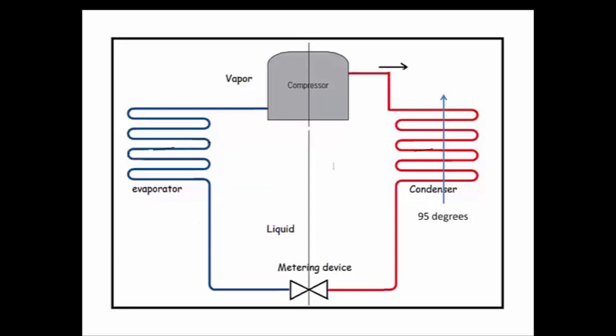Using the subcooling method should only be done on systems with a TXV valve before the evaporator. With TXV systems, the metering device works to keep the proper amount of refrigerant in the evaporator at all times and a reasonably constant superheat.